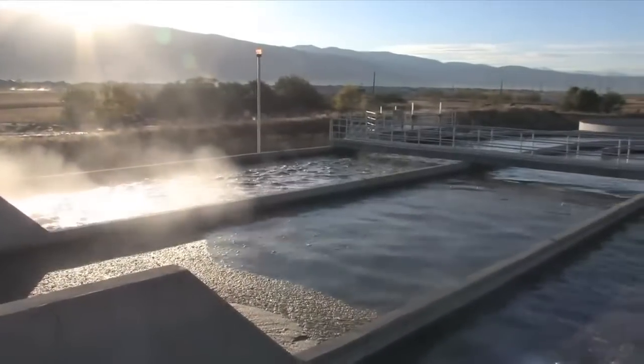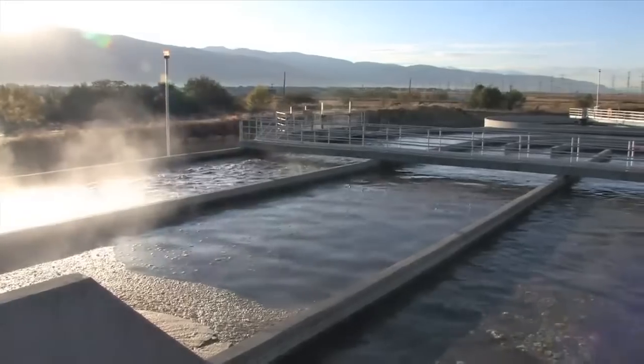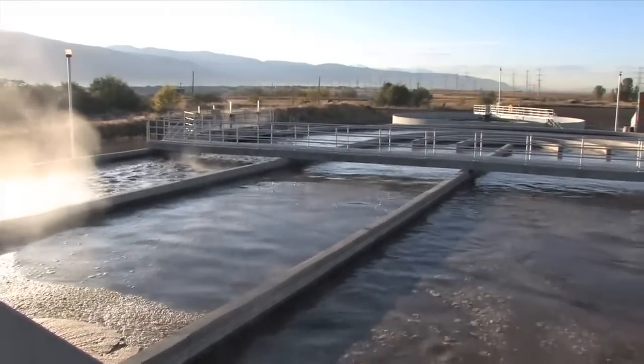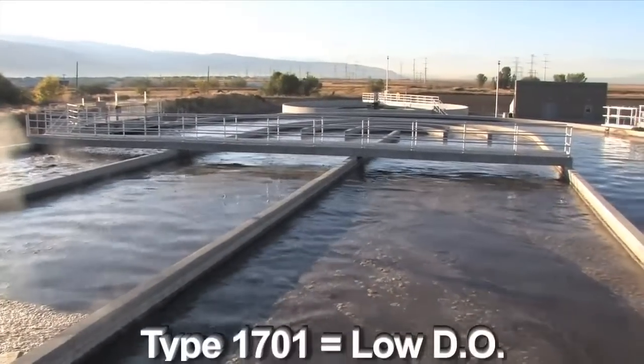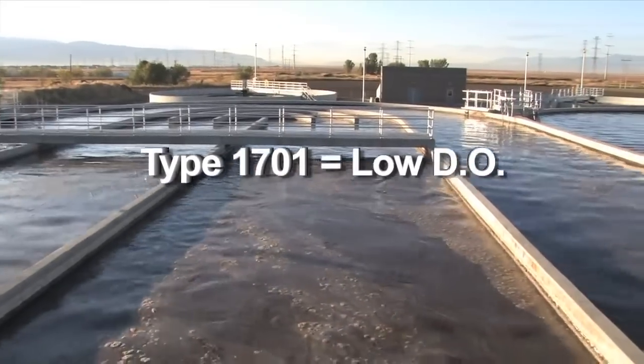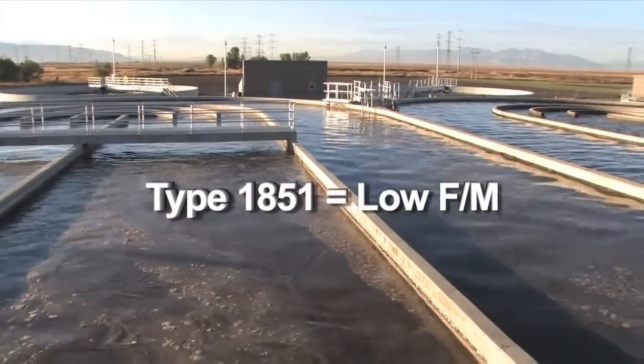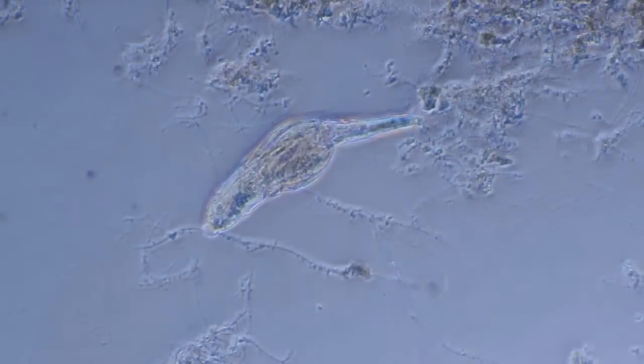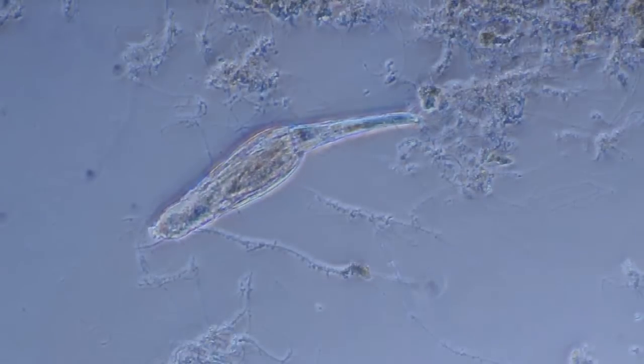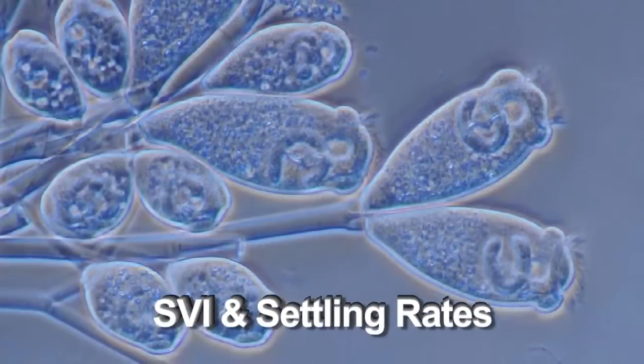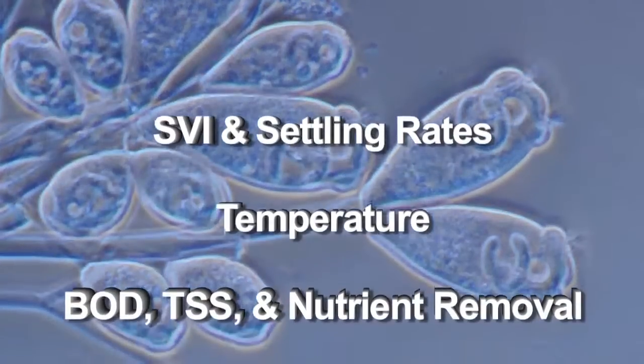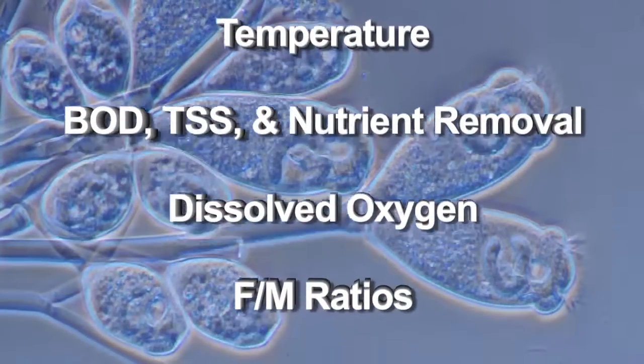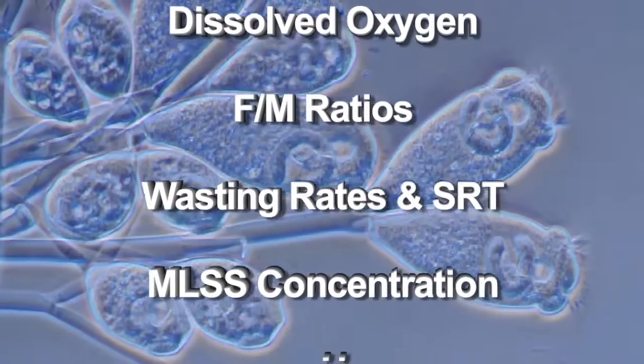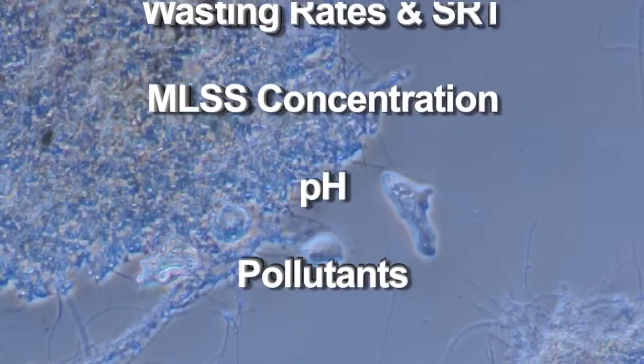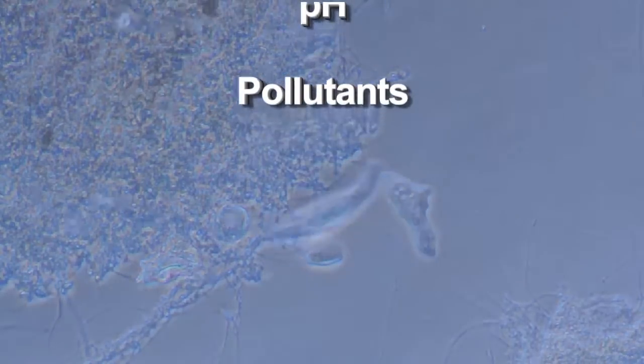The dominance of a filament indicates the operating conditions. If you want to change the biomass, change the underlying condition which supports that filament. For example, type 1701 indicates low DO, where type 1851 indicates a low F to M ratio. So what physical parameters could very well correlate with your microorganism populations? Well, the following list is a good beginning. SVI and settling rates, temperature, BOD, TSS and nutrient removal rates, dissolved oxygen levels, F to M ratios, wasting rates and SRT, mixed liquor concentration, pH, and the presence of pollutants.